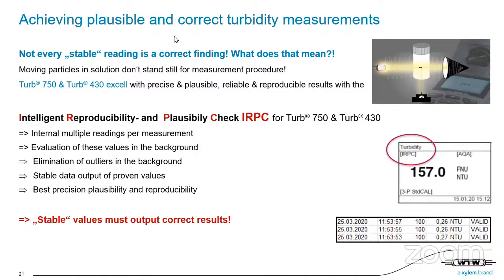To achieve good results, we have talked about the different principles and the different optical options. Now, we talk about dancing particles in a solution. So not every stable reading, so frozen reading, is necessarily a correct result or finding. Why is that, and what does that mean? As it is, they do not stand still for measurement, and we want to have a more or less good average. So first of all, we exclude all ambient and internal scattering effects by building a real nice light trap in the meter. So the light is transmitted at 180 degrees and just absorbed, also ambient light. This is our special optics, which is achieving this.